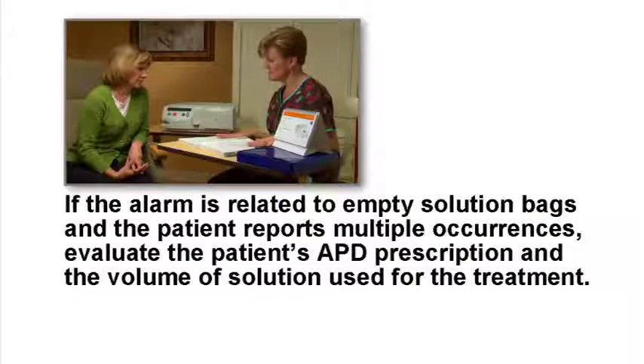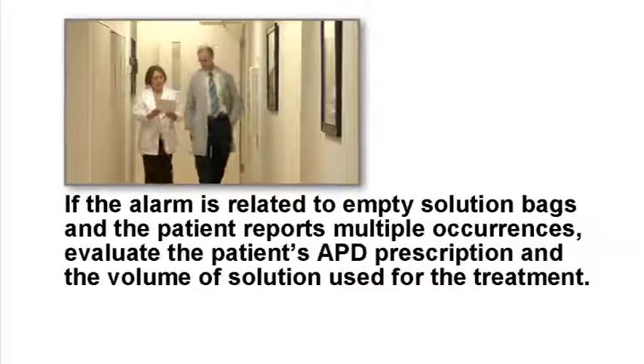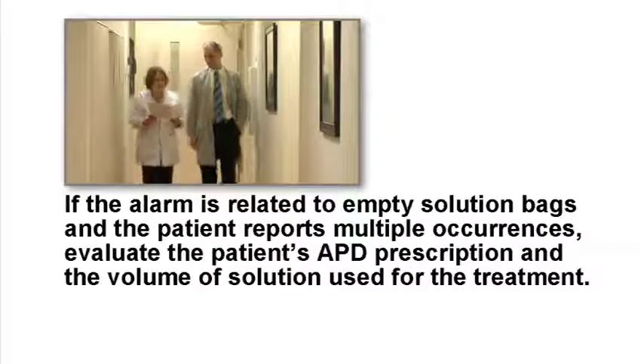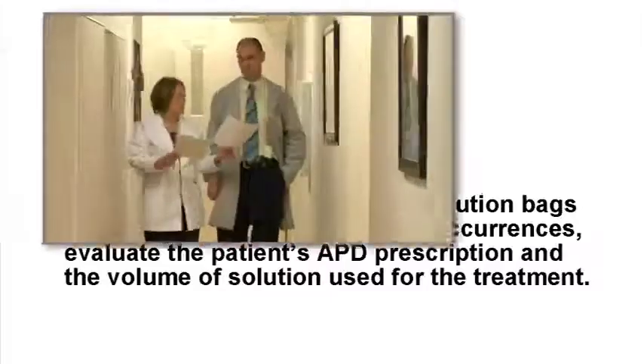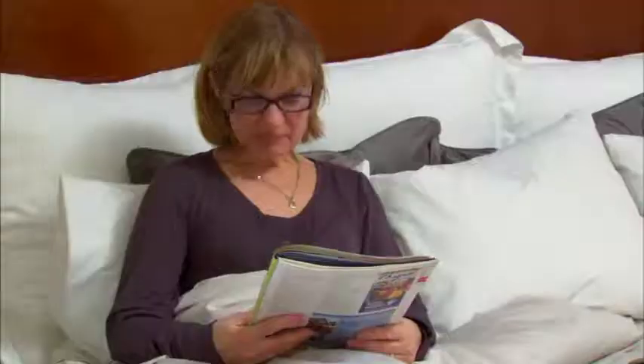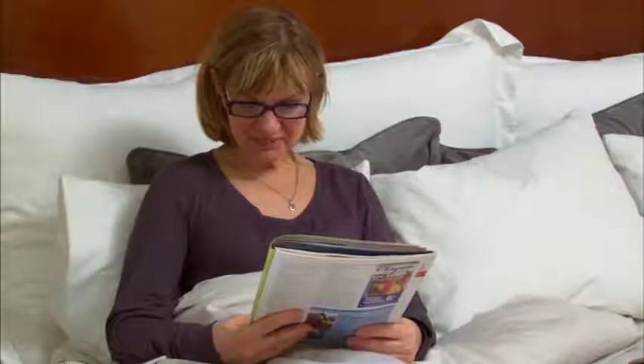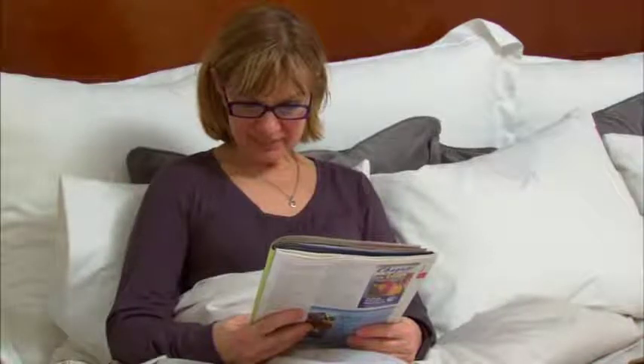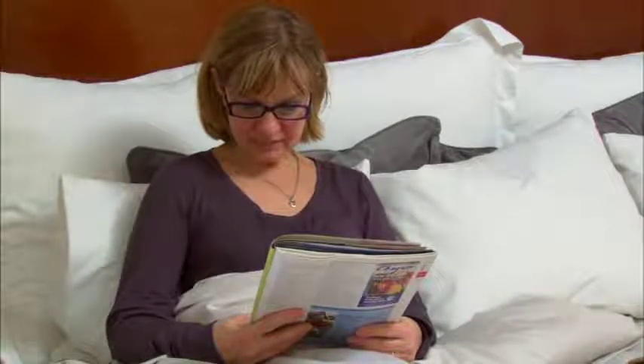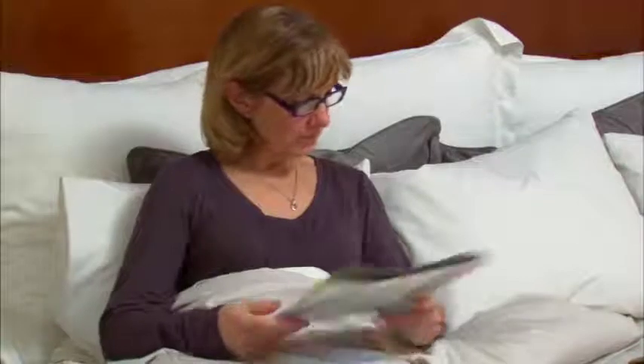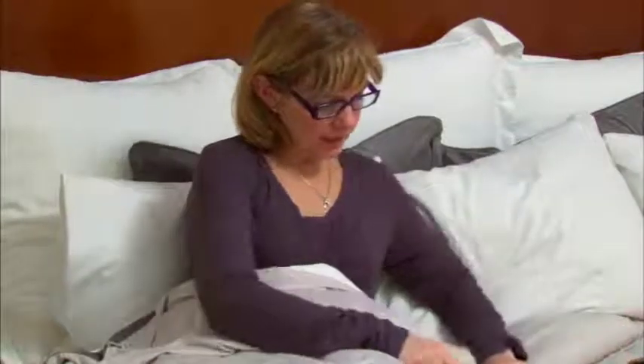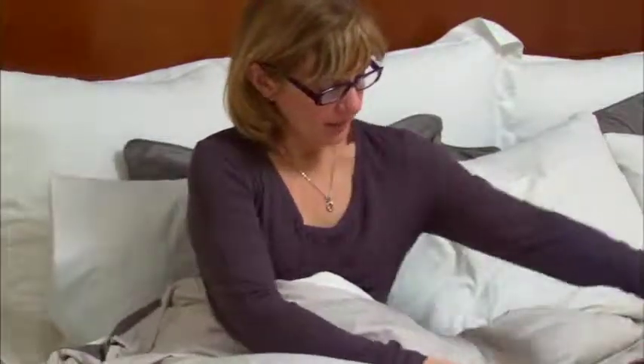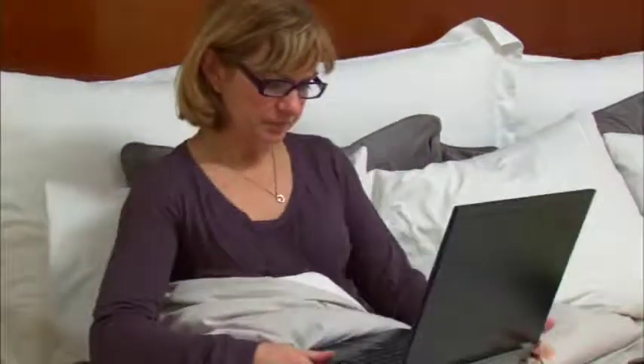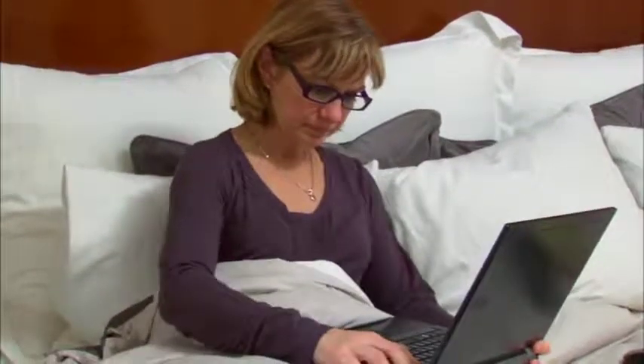If the alarm is related to empty solution bags and the patient reports multiple occurrences, evaluate the patient's APD prescription and the volume of solution used for the treatment. Since the system keeps an estimate of the amount of fluid in the patient's peritoneal cavity at any given time in the therapy, improper programming of these settings may have adverse effects leading to excess volume filled or insufficient volume drained from the patient. Remember these values.